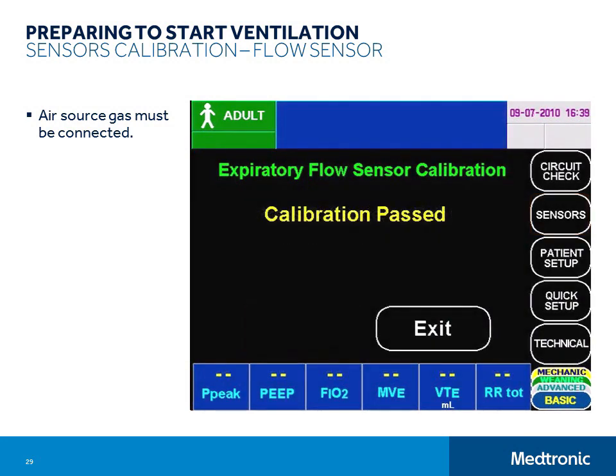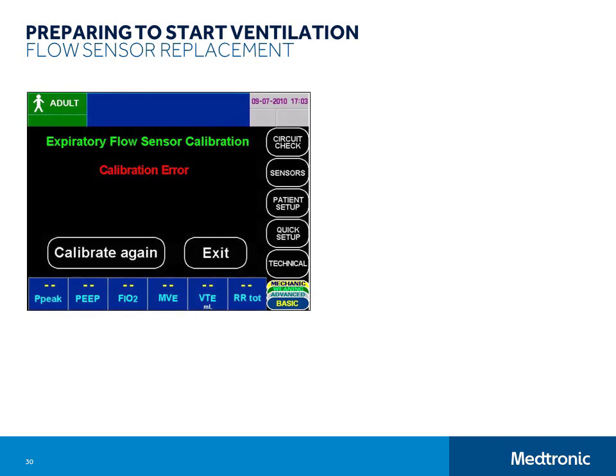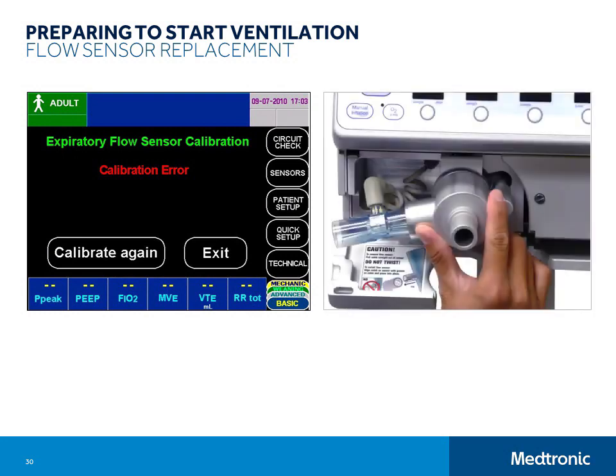Should the sensor cal fail repeatedly when the cal is performed according to directions, you will need to change the flow sensor. If the ventilator is in use, provide alternate ventilation to the patient. Then follow these steps. Open the front panel door on the left lower front of the ventilator to expose the exhalation valve and flow sensor. If you find that it makes it easier for you to access the flow sensor, you can remove the exhalation valve from the body of the ventilator first by releasing the retaining latch.